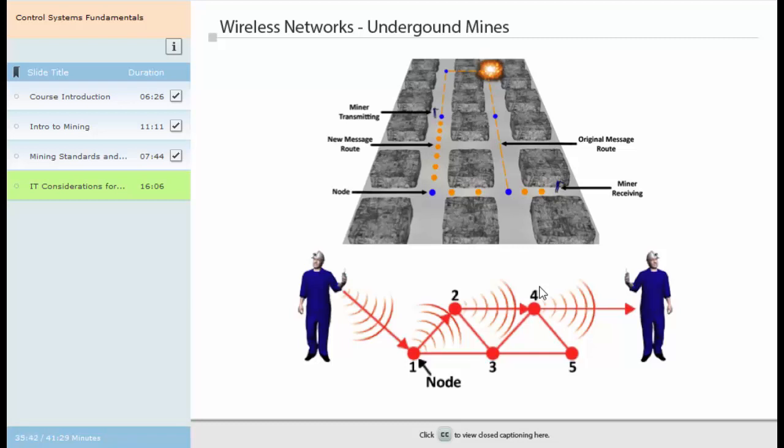Mesh systems should be deployed to cover expanding areas and to provide redundant paths that can protect network connectivity if rock or debris blocks one of the paths. In addition, devices need to be rugged and the system needs to be operable through the use of battery power when necessary. Successful installation in an active underground mine requires long-distance network access for voice, location tracking, and video monitoring.